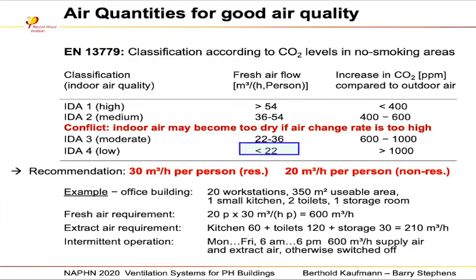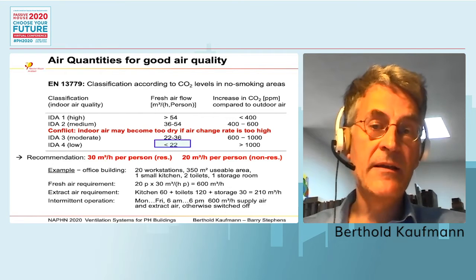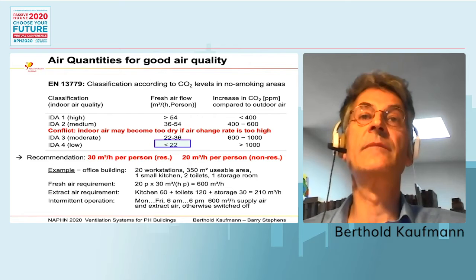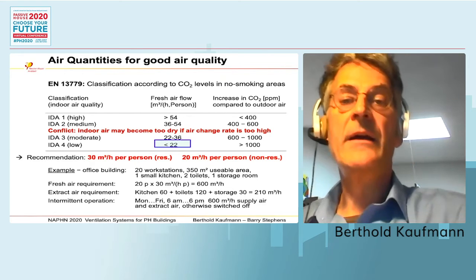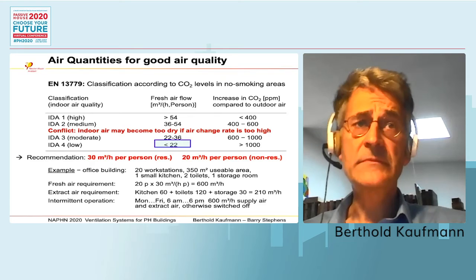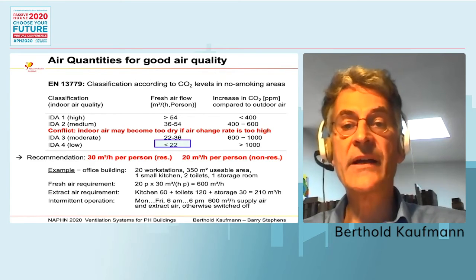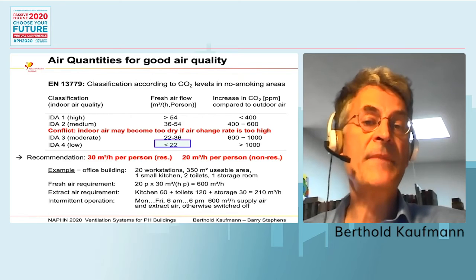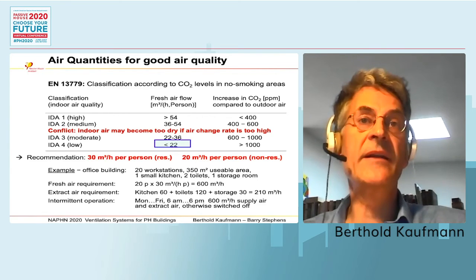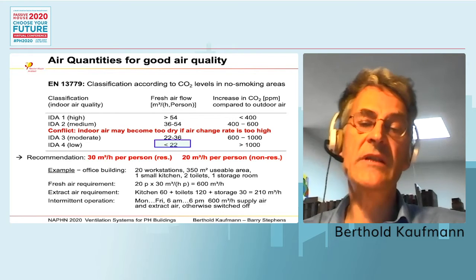That means the recommendation is only 30 cubic meters per hour per person for residential buildings, and maybe 20 cubic meters per hour per person for non-residential buildings, so for classrooms or meeting rooms where many people are in. If you have more than this, you must be aware that there will be too dry air in wintertime. If too much airflow comes in, this will dry out people and they will complain afterwards. For this, now Barry will explain a little bit more in detail why ventilation and how to go for it.